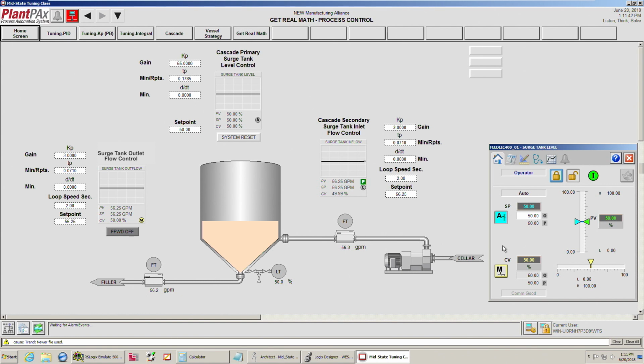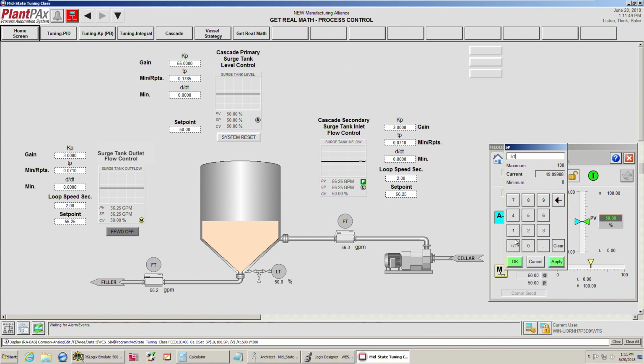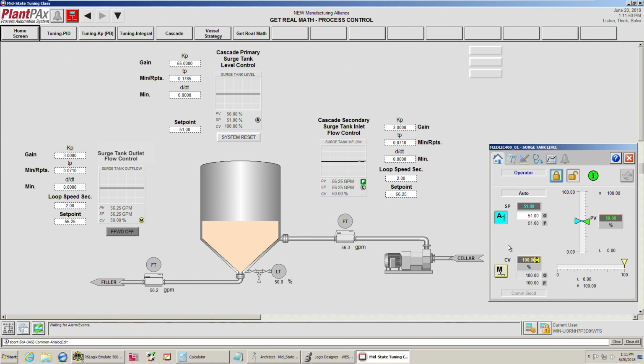Proportional, or gain, is relatively easy to understand. When a set point is entered into the controller through a graphical faceplate, much like a home's thermostat, an error is instantly produced between the process variable and the new set point. The error is multiplied by a scale factor, the proportional gain, and immediately applied to the output. The process variable will move in the appropriate direction to begin correcting the error.